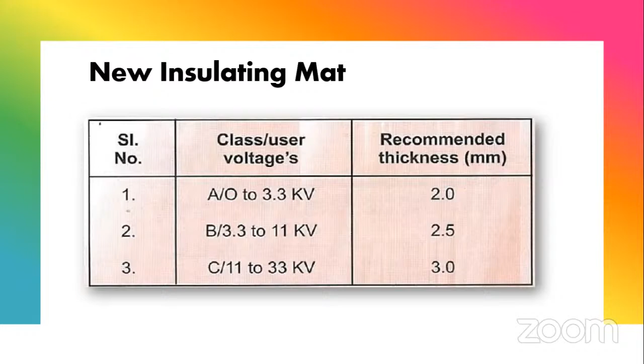In this standard, there are three types of insulating mats. Type 1 is about 2 mm thickness, type 2 is 2.5 mm, and type 3 is another section. Based on the voltage - if your voltage is between 3.3 to 11 kV, you will go for 2.5 mm thickness mats. So based on the voltage, you choose the mats.